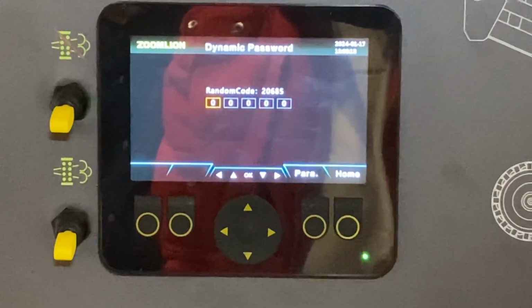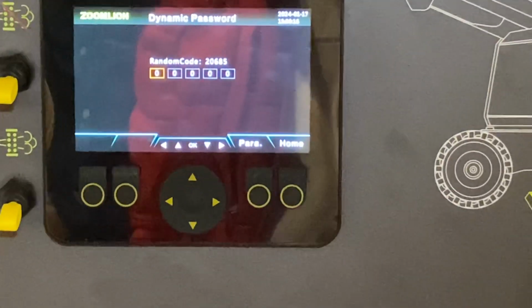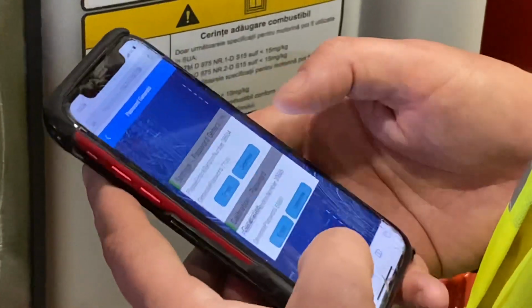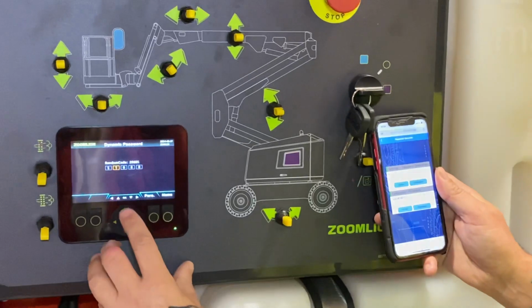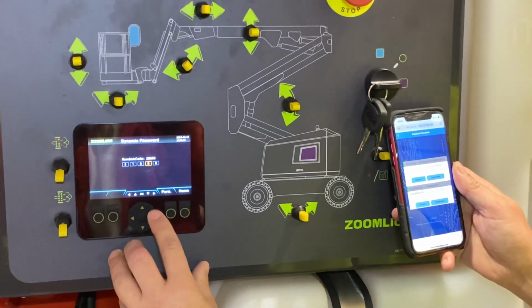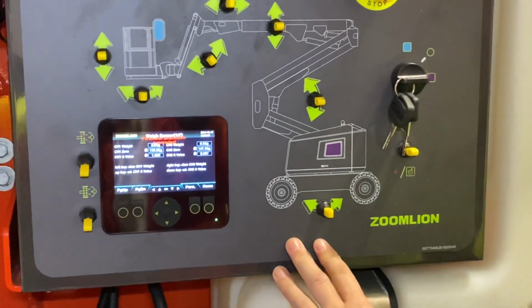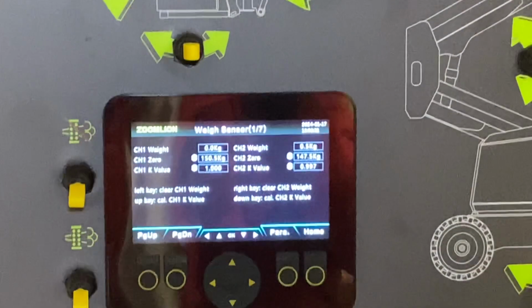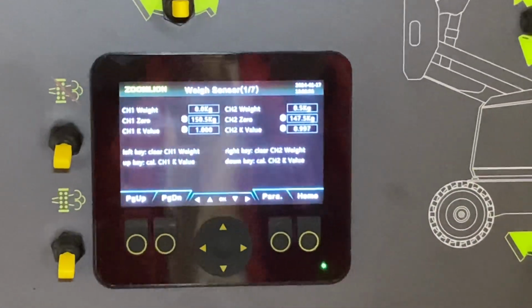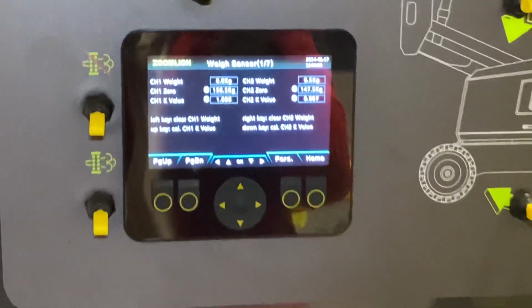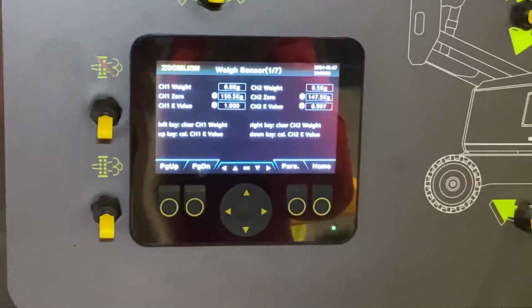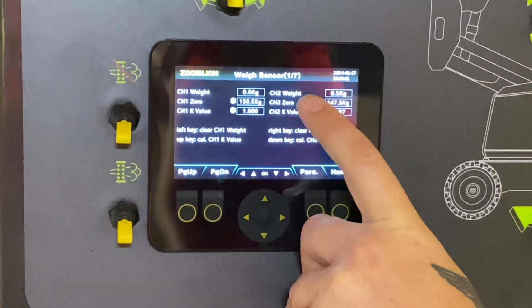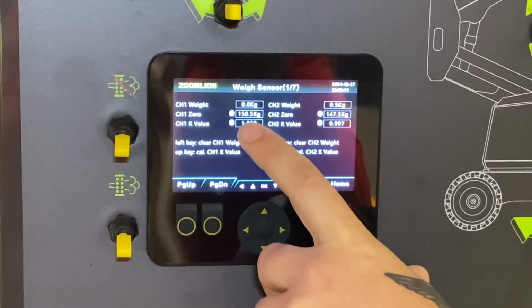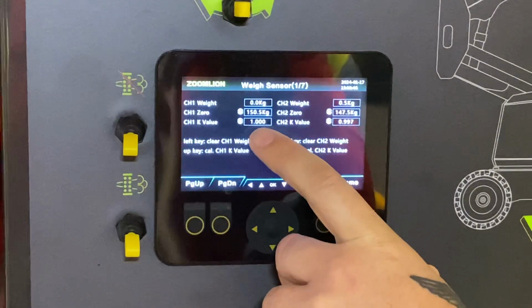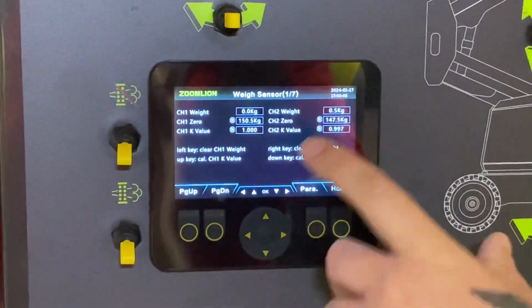So I generate a different password. Okay, so you can see now we've entered the calibration menu. Okay, so in here, the first menu option is page 1 of 7, which is the weight sensor. Okay, we only ever calibrate and zero the channel 1 weight and the channel 2 weight. We do not adjust and set the K values. Okay, they should always be between 0.9 and 1.1, which we can see that they are.